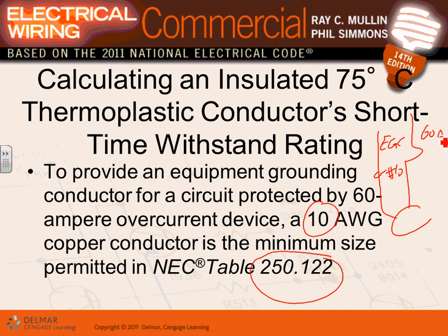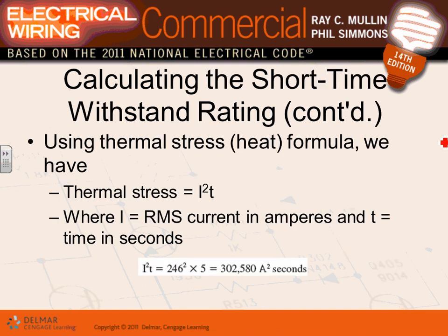You can cook that conductor because of the withstand rating of this conductor. So here's a calculation that we need to do, guys. The calculation that we did for this conductor, number 10. Now Adam, here's my number 10 conductor, like I said, 60 amps. Here's my equipment. Here's my equipment grounding conductor.